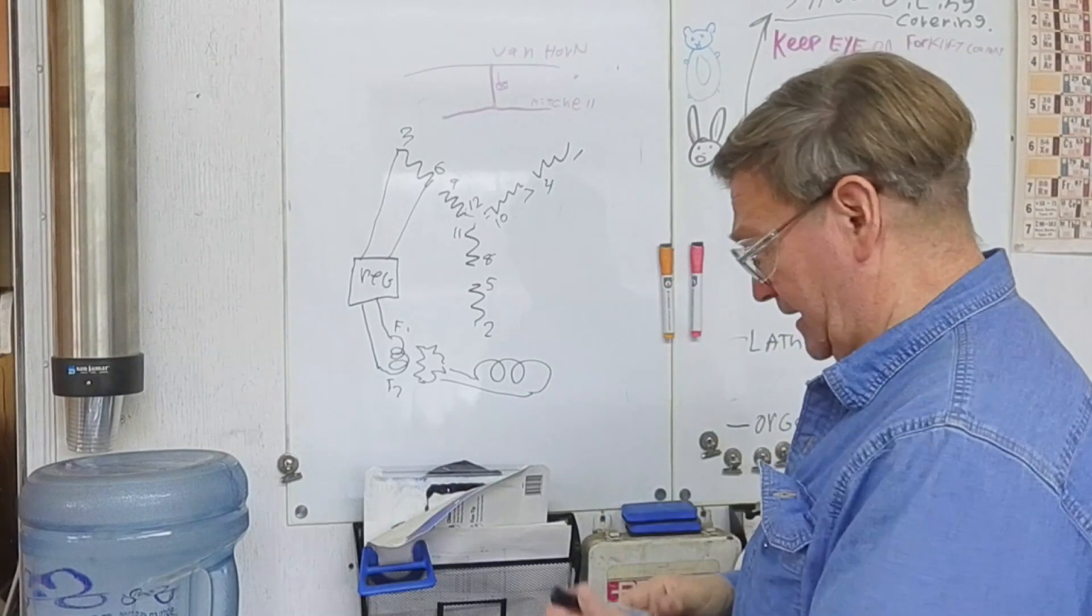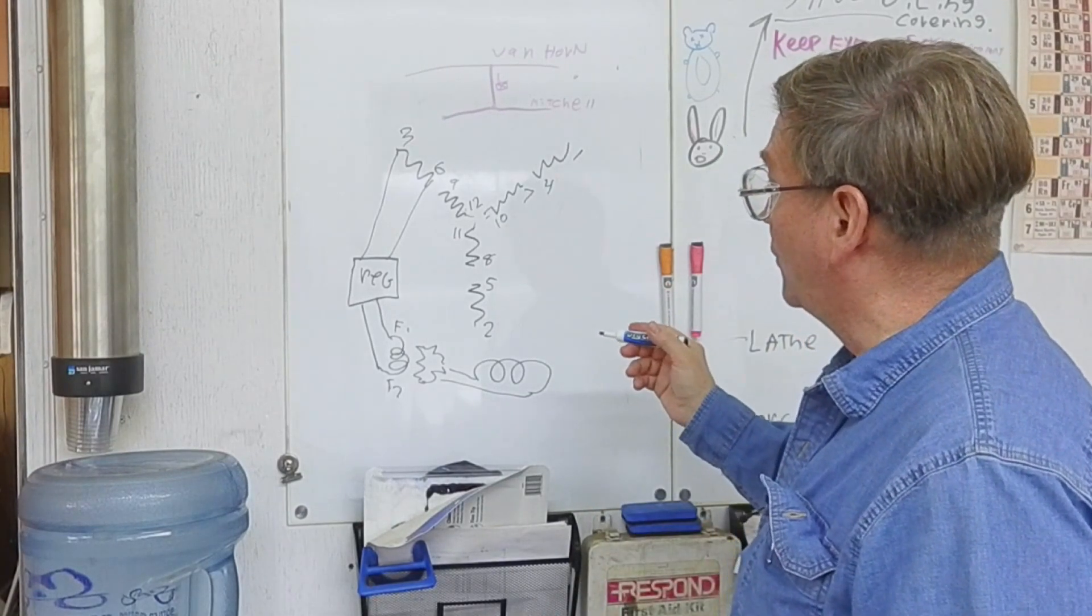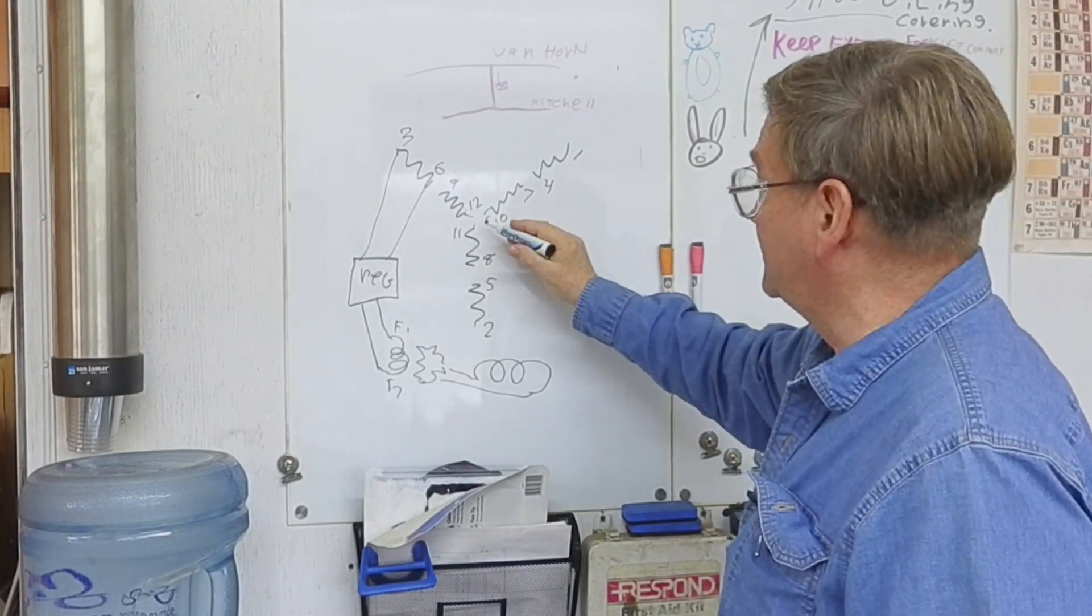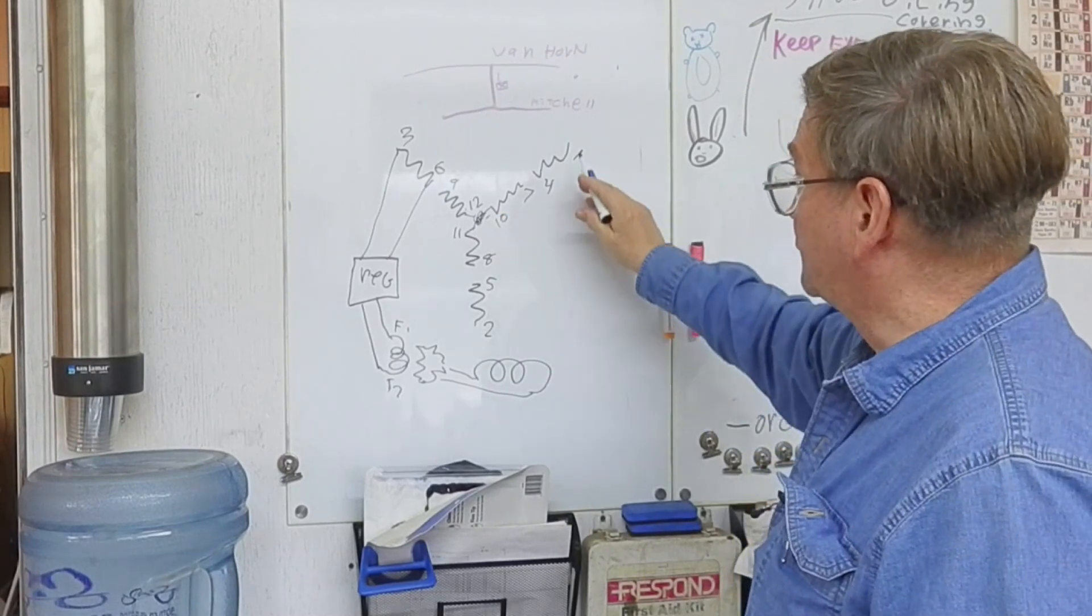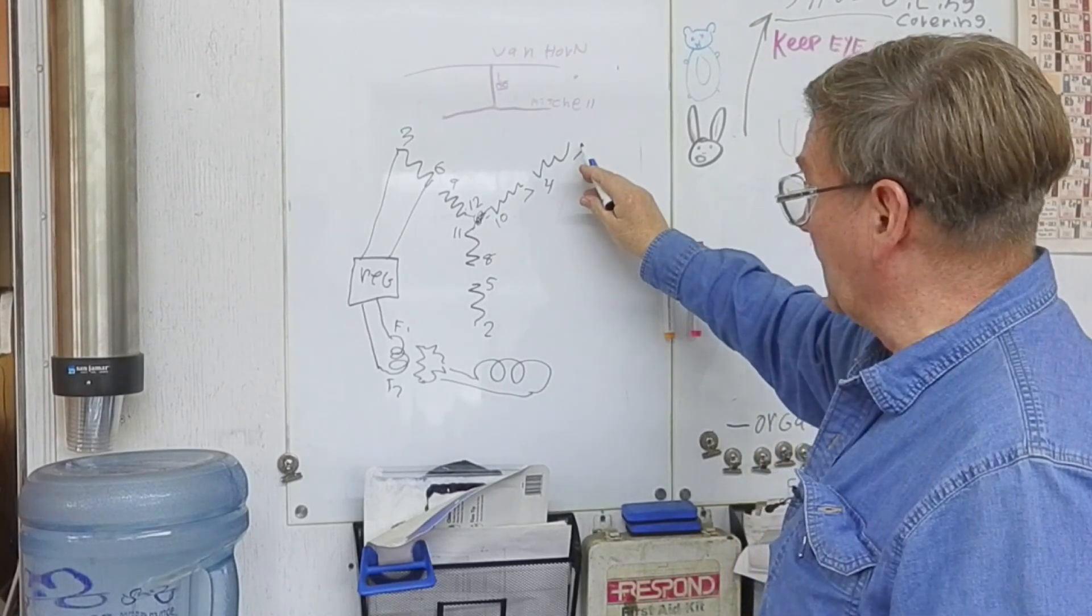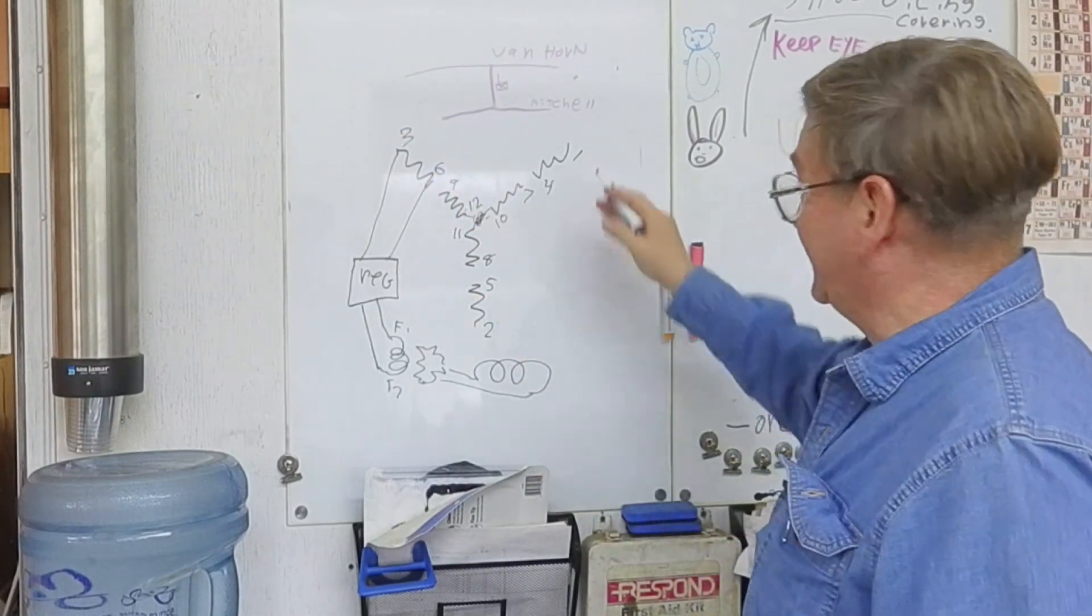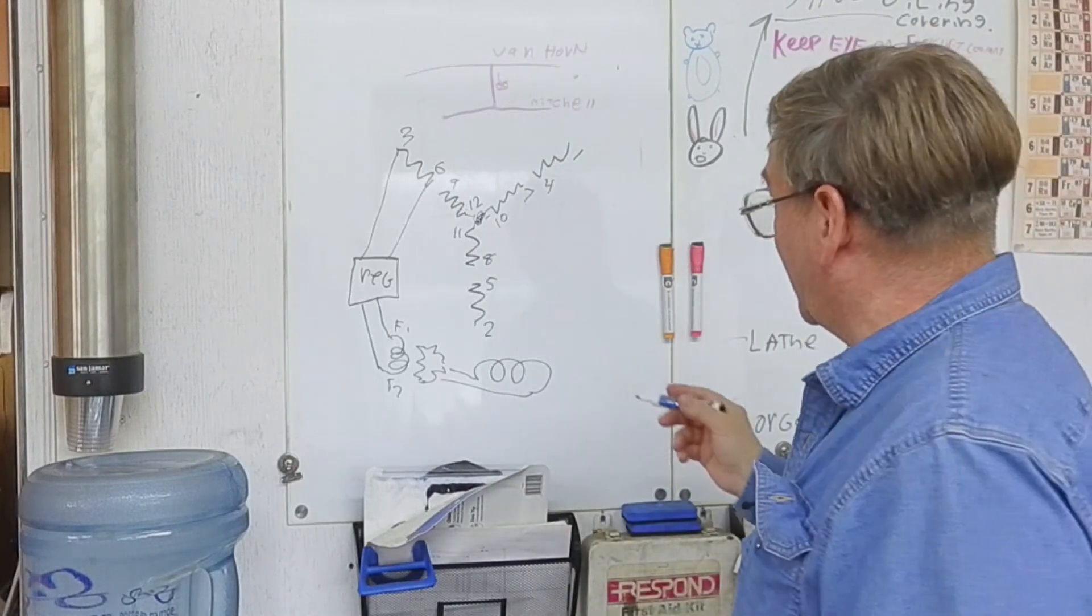If we're running a generator or motor, let's say we're running a generator and it's 480 volts. So we tie all of these together. You traditionally put your lines on one, two, and three. These are T numbers, which would be terminal number. And then you go L for your lines, but you just normally go one, two, and three. So that you keep the numbers the same going into your line.